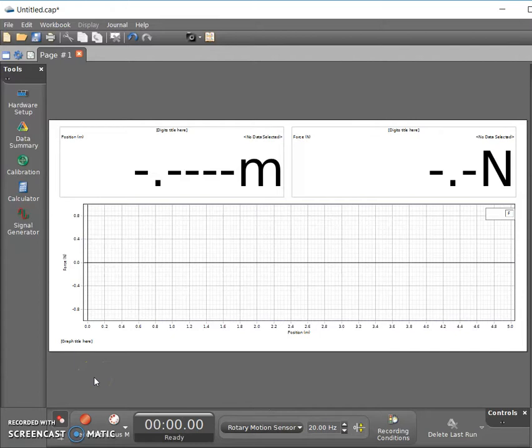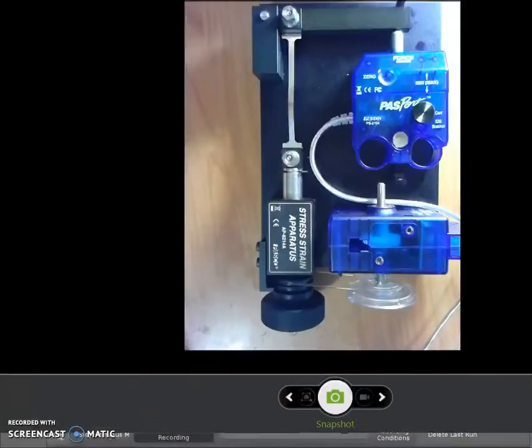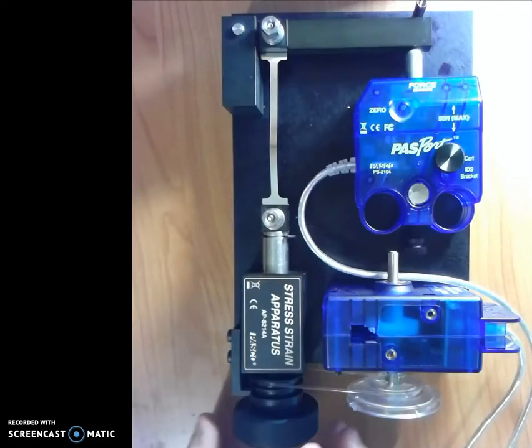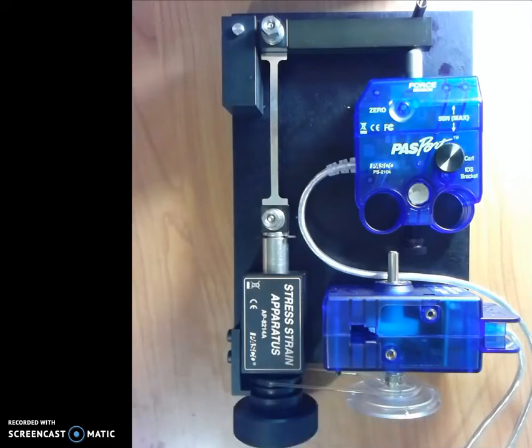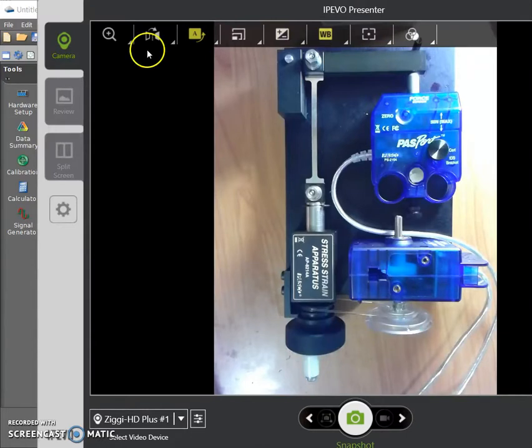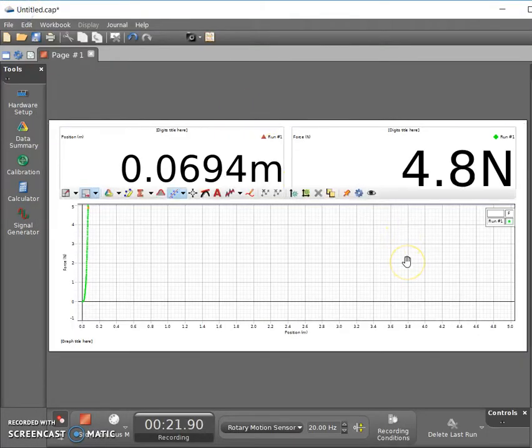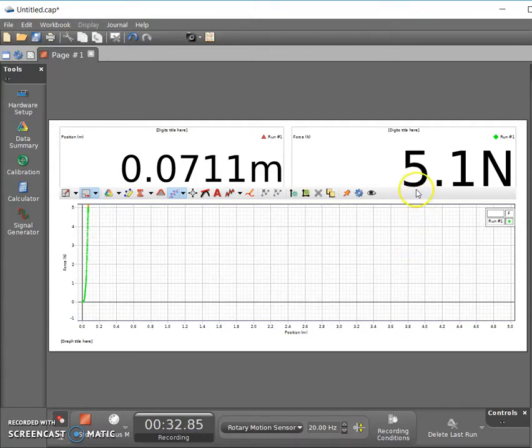So I'm going to hit the record button, and I'm going to bring this screen up so that you can see it here. I'm going to just start turning in a clockwise direction. You can see the sample coupon starts to absorb some of that force. Now let me turn back in this direction. Okay, now what PASCO recommends is that you start at 5 newtons. So I've got now the sample coupon preloaded to just over 5 newtons.